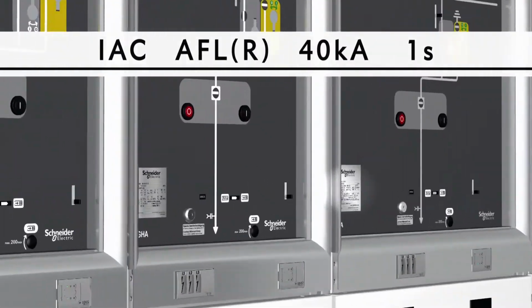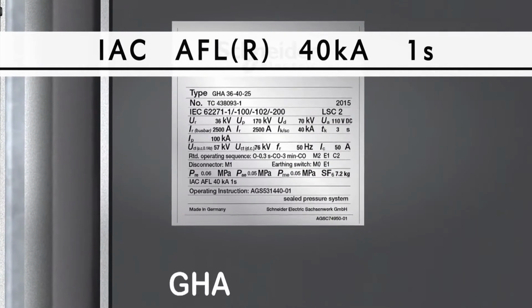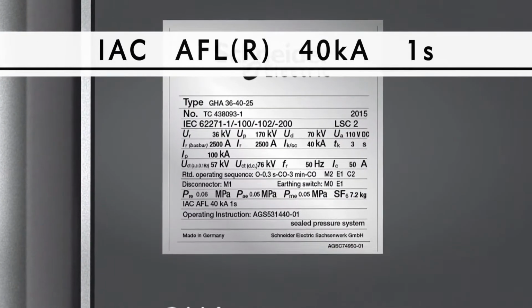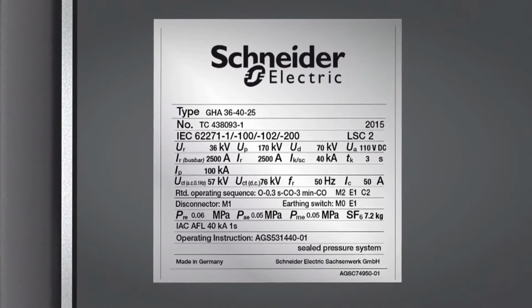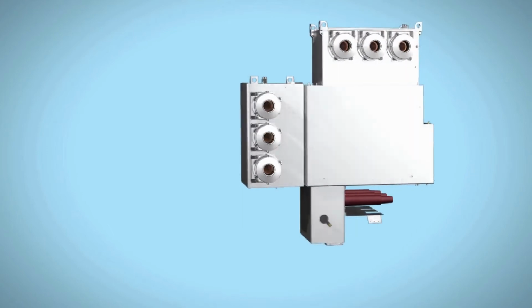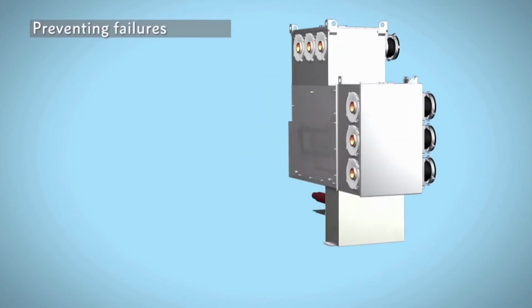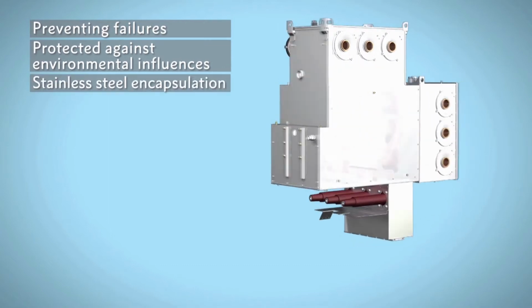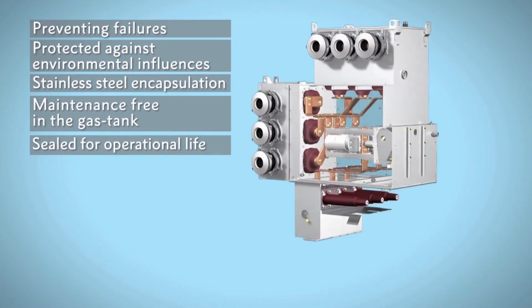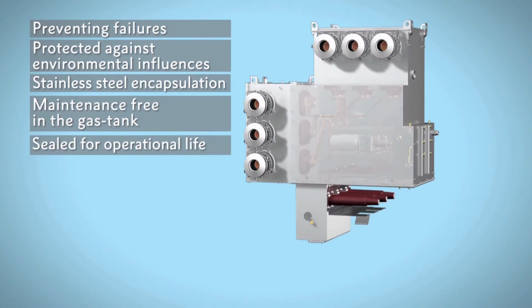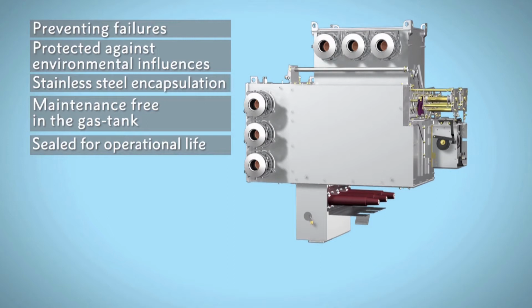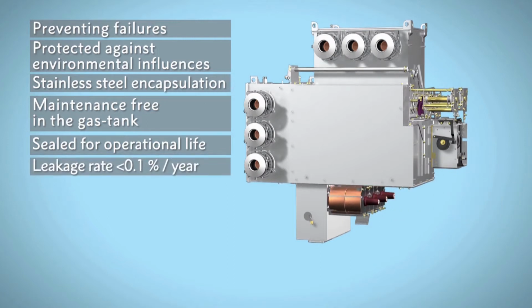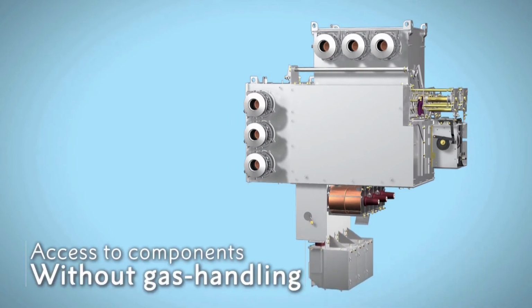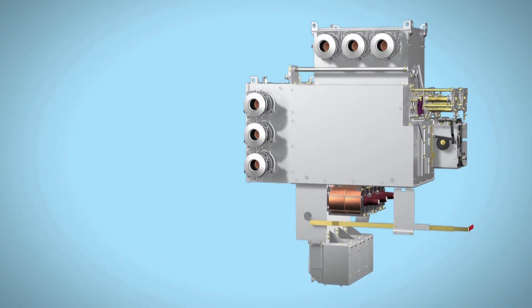Successful type testing for internal arc classification AFL or AFLR up to 40 kiloamps short circuit current for a duration of 1 second ensures a high level of operator safety. Schneider Electric gas-insulated switchgear is designed to prevent failures. All high-voltage parts are protected against environmental influences in a stainless steel tank, making them maintenance-free for an operational life of more than 30 years. In compliance with IEC 62271-1, the GHA tank is a sealed pressure system, leakage tested for a leakage rate of less than 0.1% per year. For accessibility without gas handling, components like the drive mechanism and instrument transformers are consistently located outside the tank enclosure.